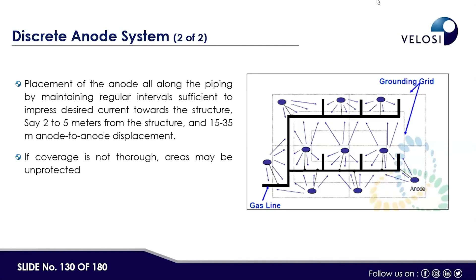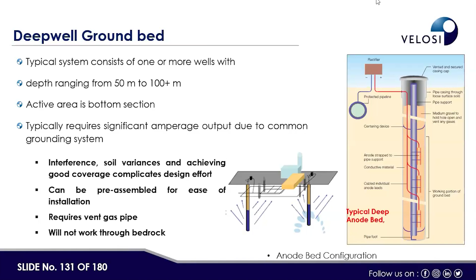Then there's the deep well anode, comprising 10 to 20 anodes installed vertically. One deep well anode can protect a long distance pipeline up to 40 kilometers, or it can protect tanks, like 4 to 5 tanks of 50 meters each, or one larger tank of 100 meters, using one deep well ground bed. It depends on which type of anode bed will be economical and more accurate for the situation.